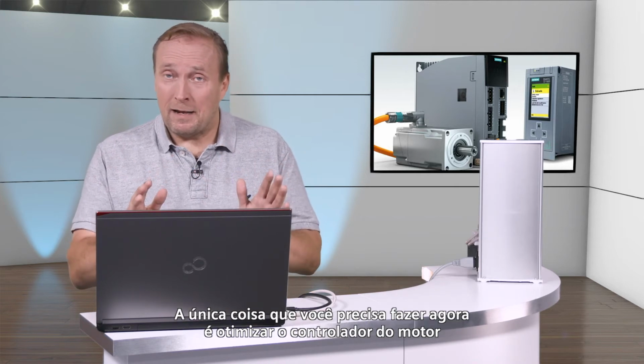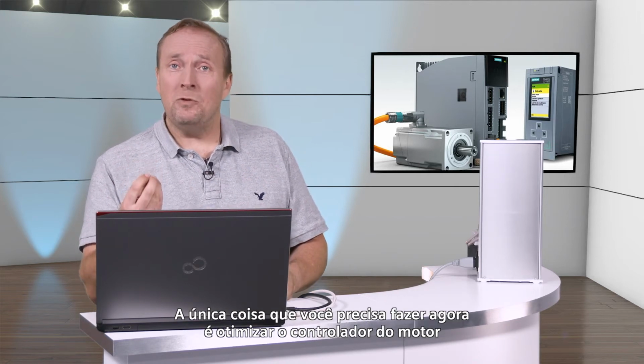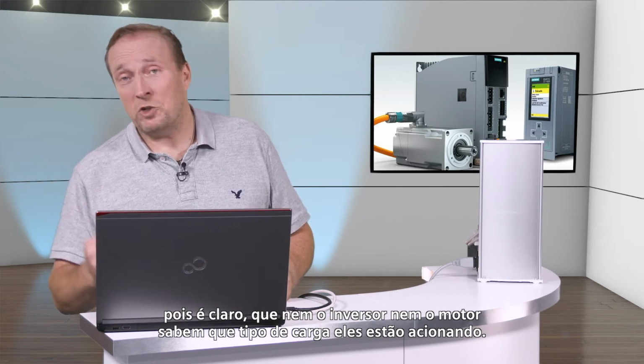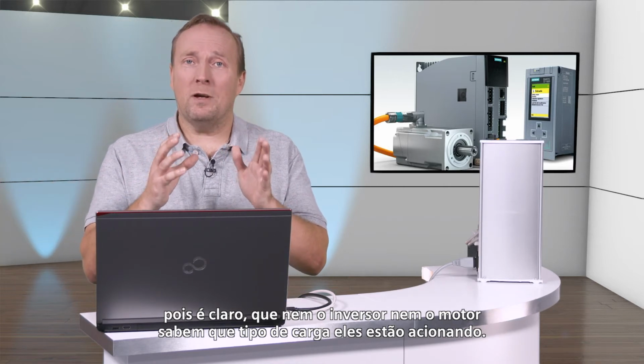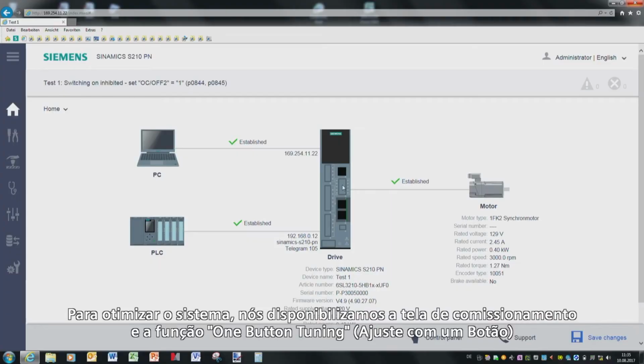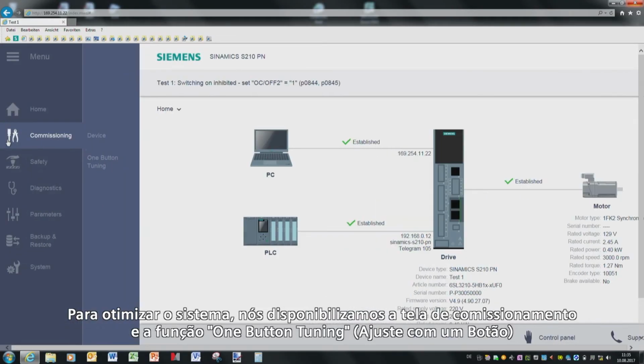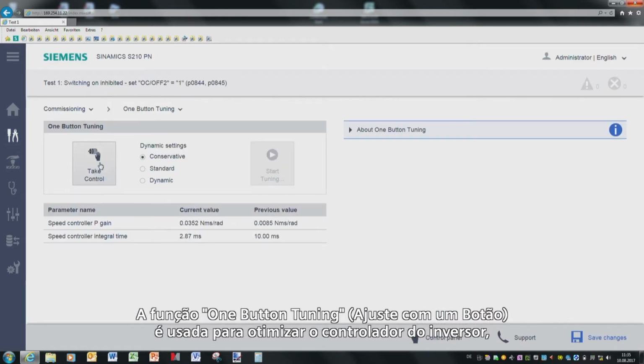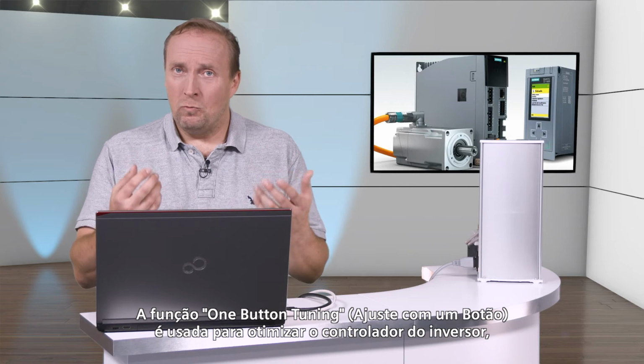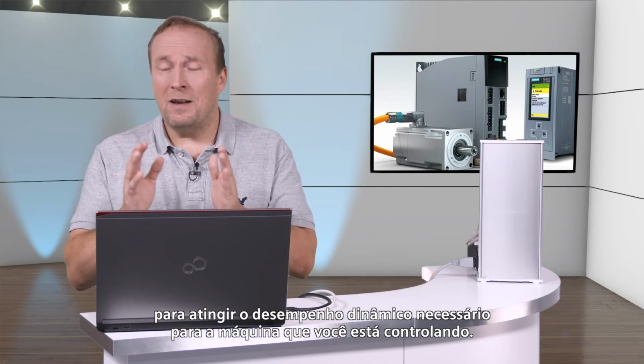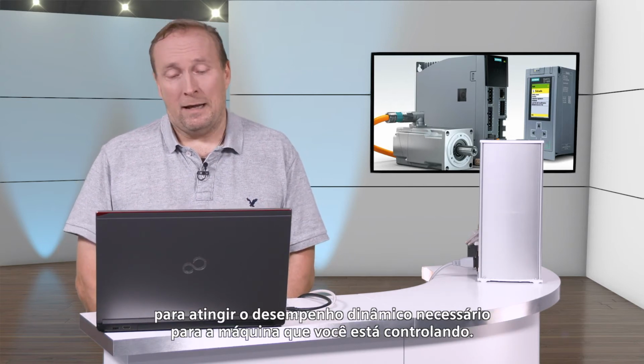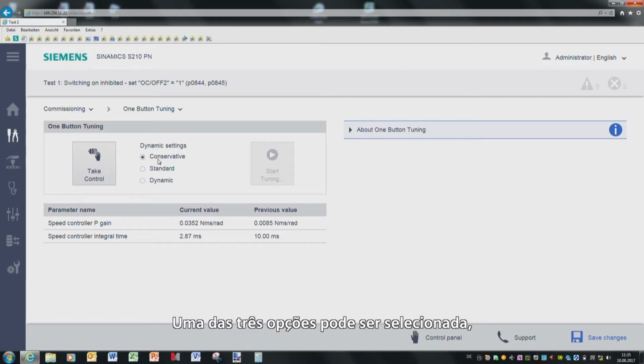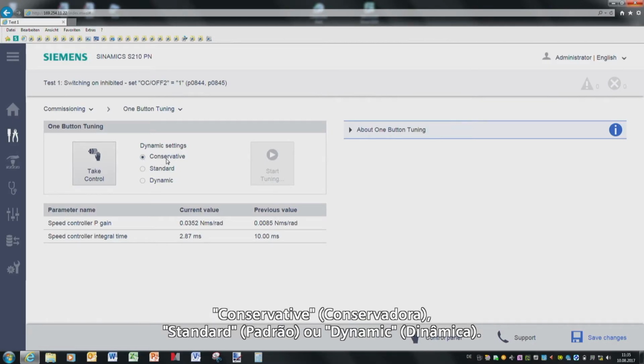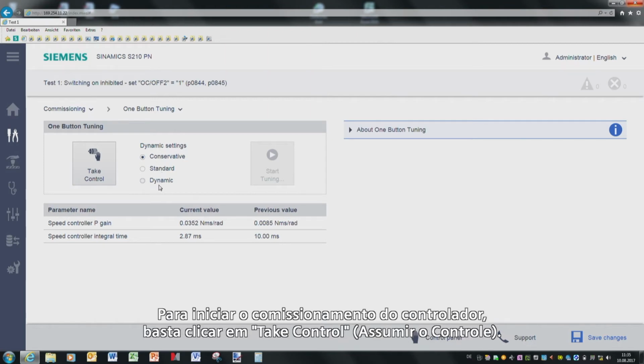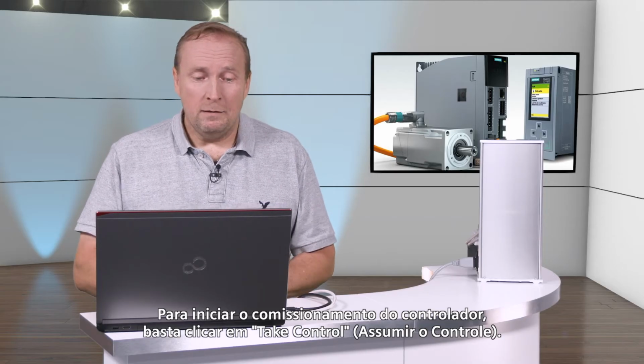The only thing that you have to do now is optimize the motor controller, as of course the converter and motor do not know what sort of load they are driving. To optimize the system, we have provided a commissioning screen and the one-button tuning function. The one-button tuning function is used to optimize the converter controller in order to achieve the required dynamic performance that you need for the machine that you're controlling. One of three options can be selected: conservative, standard, or dynamic. To start commissioning the controller, simply press Take Control.